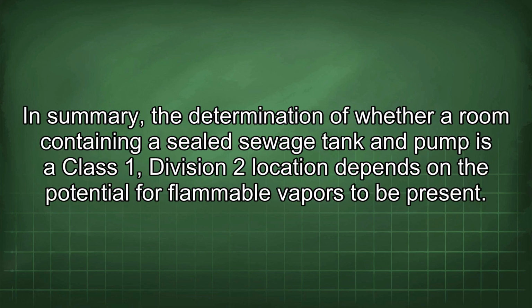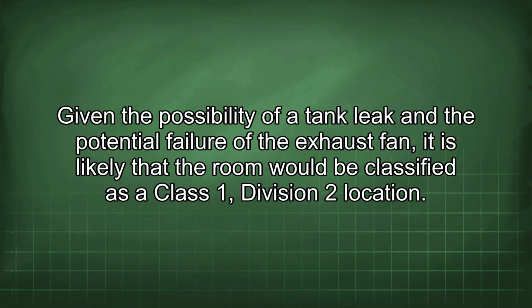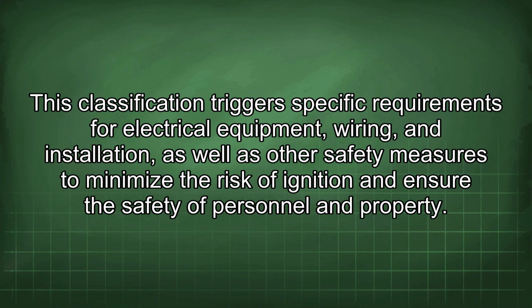In summary, the determination of whether a room containing a sealed sewage tank and pump is a Class 1, Division 2 location depends on the potential for flammable vapors to be present. Given the possibility of a tank leak and the potential failure of the exhaust fan, it is likely that the room would be classified as a Class 1, Division 2 location. This classification triggers specific requirements for electrical equipment wiring and installation, as well as other safety measures to minimize the risk of ignition and ensure the safety of personnel and property.